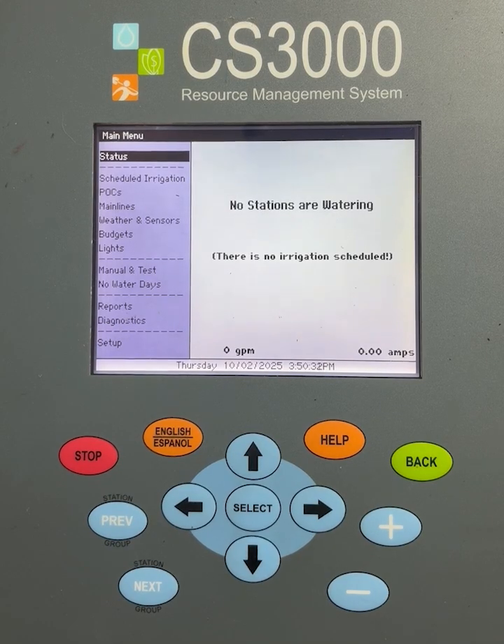So the first thing we're going to do, obviously, this is assuming that you have your master valve and flow sensor wired to the controller. You also need to know what type of master valve you have, normally open or normally closed, and what type and size flow sensor you have. For example, 2-inch plastic, 2-inch brass, 2-inch ultrasonic, etc.